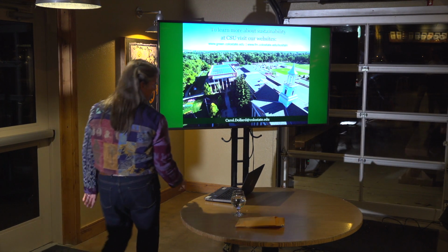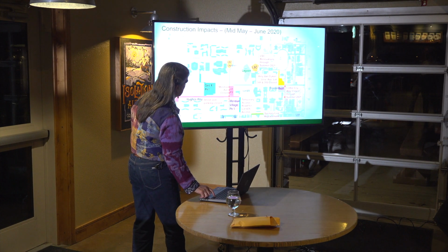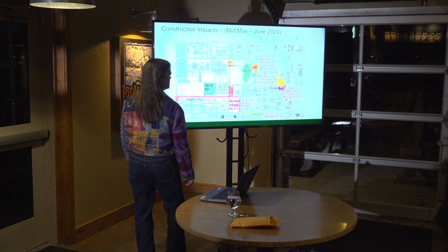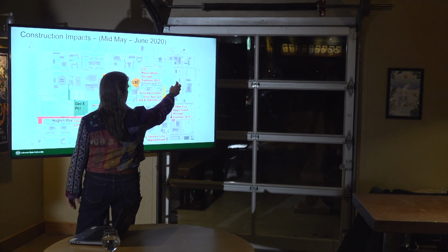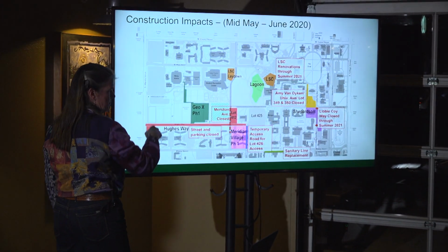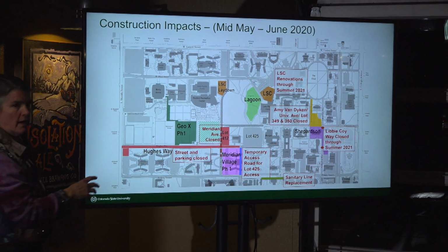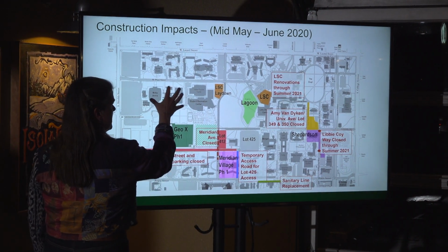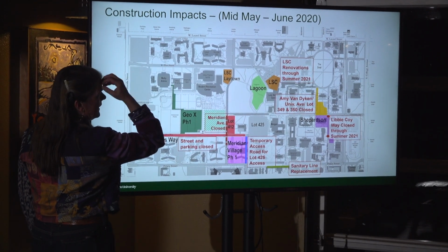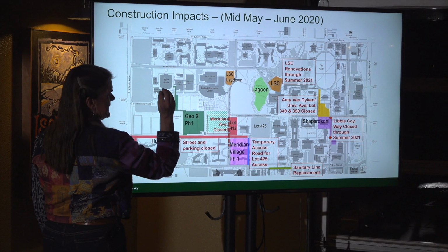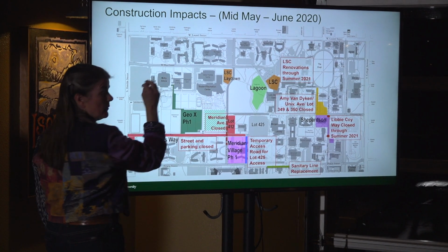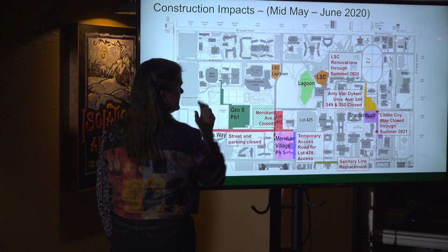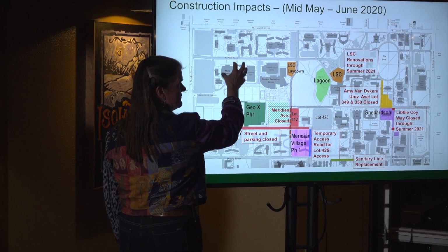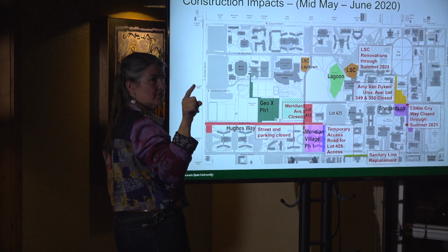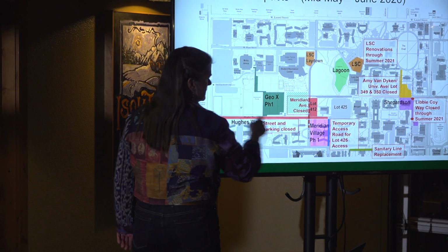But in terms of percentage of the whole campus, what's really interesting — let's go back to my map a minute, I'm going to make you guys dizzy. Here, look, this is a map, this works. Remember my steam plant's way over here, and the line losses in this mile-plus of steam lines on this side of campus. Once Moby comes off — and they're working on Durrell and a couple more, Rec Center's already off steam — very shortly after we finish Moby, we will no longer need the steam system on this side of campus. So not only will I save the natural gas usage of this building, but I'll save all the losses in those steam lines from here to here.